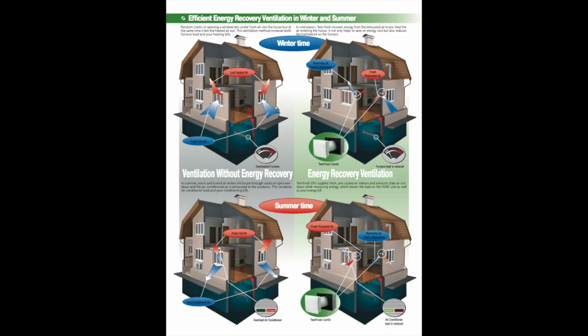Another way to address outside air in a historic building: I know there are some manufacturers out there that make through-the-wall energy recovery ventilators, where you bring in some outside air, run it through some sort of ERV core, where you can do some actual energy exchange, and filter the air and bring it into the space. They have these for single rooms, which is useful for apartment buildings or maybe office buildings that have direct access to the outside wall. So that's another way of bringing in outside air in a historic building.